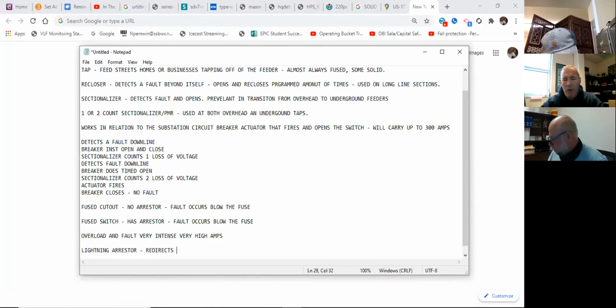Okay. If I have overvoltage, it goes to ground. So if I have a line that's 7,200 volts, I'm going to have an arrestor that's typically rated to 8,100 volts. Once it reaches that rating of 8,100, because of the lightning strike, or more than 8,100, it's going to take that lightning strike to ground. It won't proceed into the transformer. So lightning arresters redirect overvoltage, and that goes to ground.